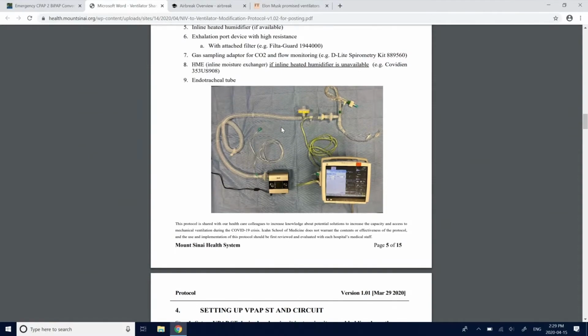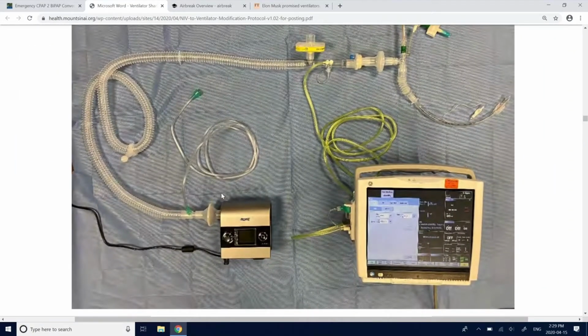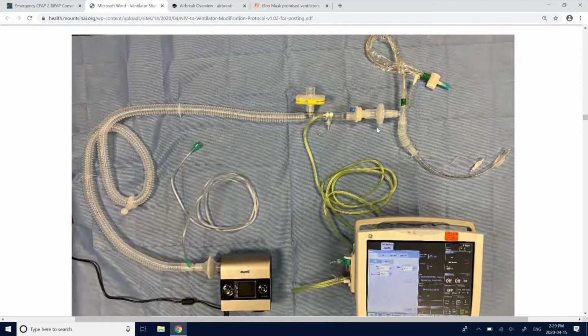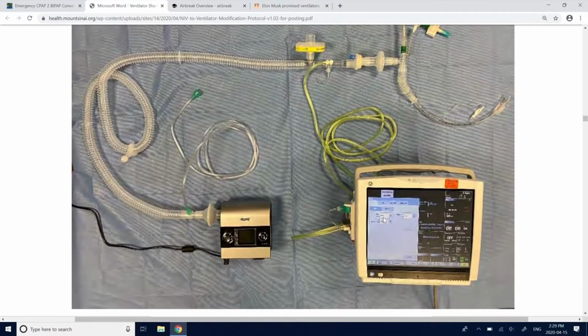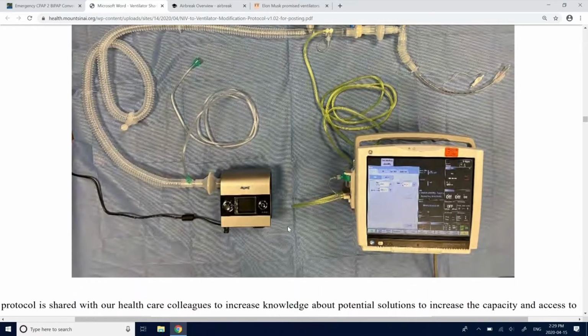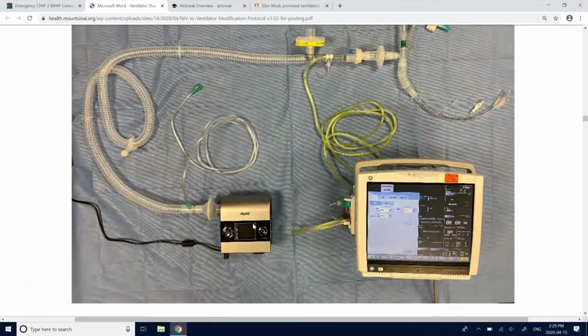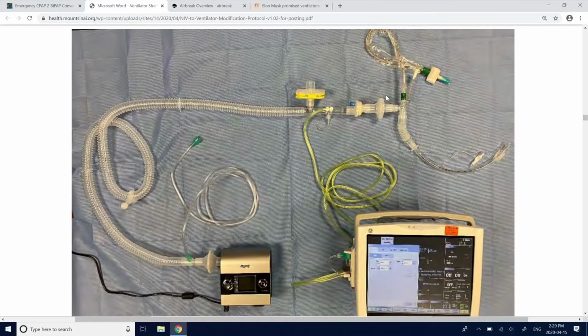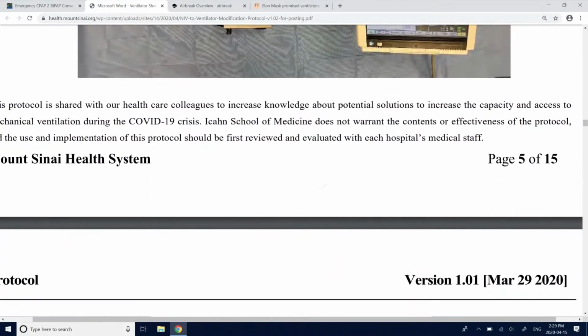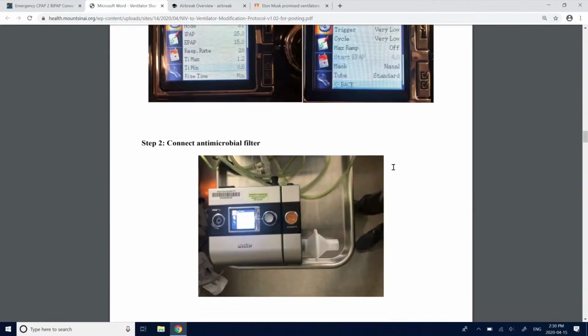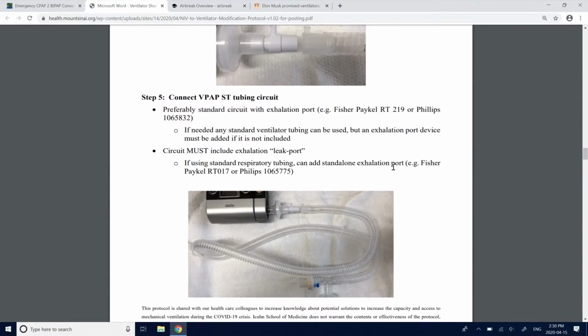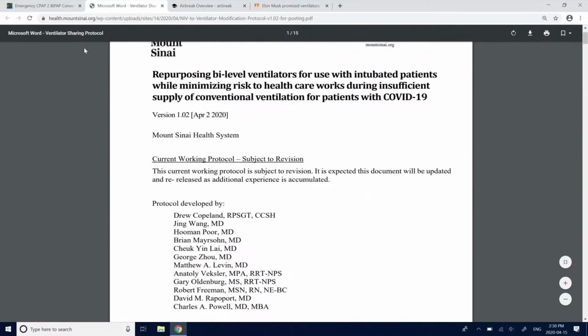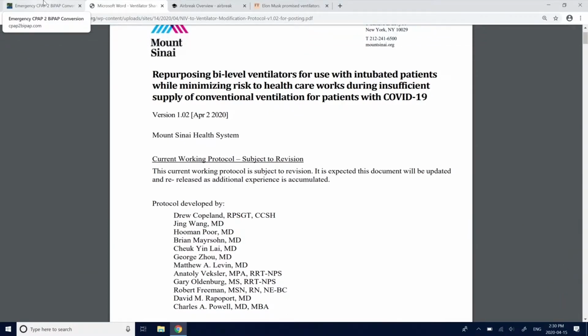And they basically added, so the actual ventilator is the little thing on the bottom left, and the rest of this is some tubing. One other issue is being able to insert oxygen, so that's some of the other stuff you can do. They have monitors because these machines are not designed with alarms or anything. They're normally not critical for these types of operations. So there's an external machine, and if you had more of them, that can serve as the alarm, as well as viral filters and stuff like that. And in this case, this can be used with intubated patients. There's other work being done to source viral filters for the actual machines themselves. So there's a bunch of ongoing projects related to that.